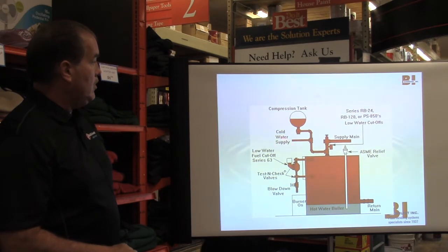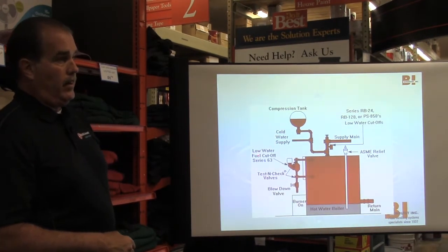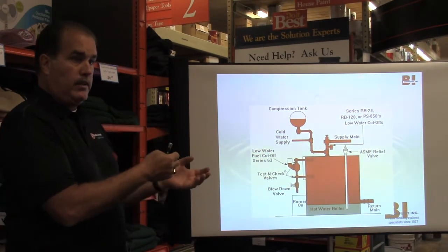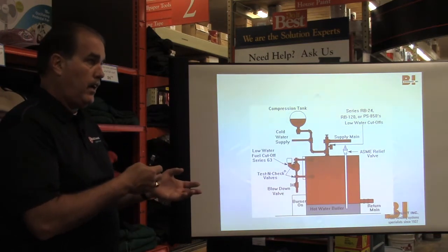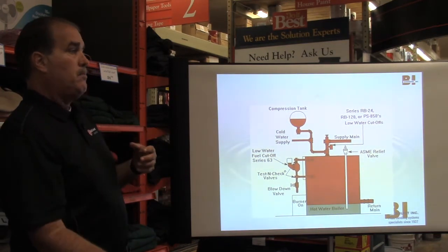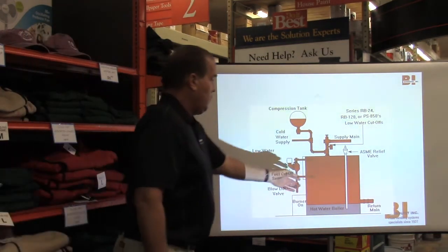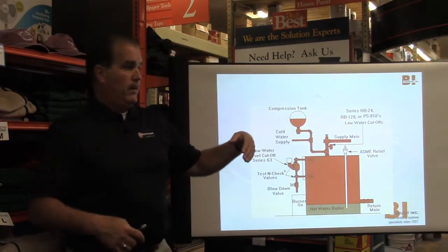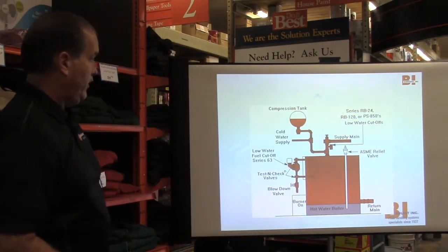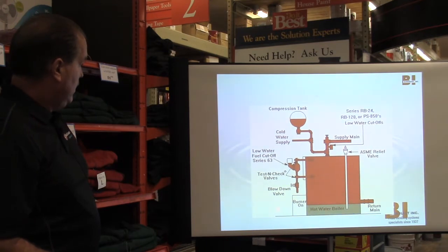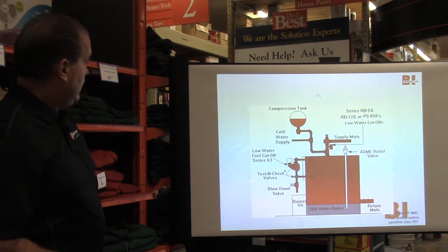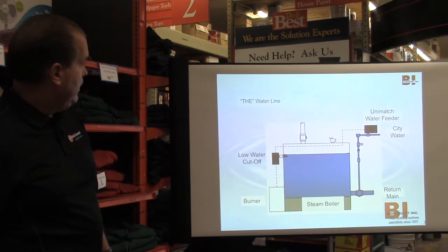This is your inlet water. You usually will have a makeup regulator that actually lets the water in. It's usually set for like 12 psi or whatever. So if the system water on the boiler side drops low enough, it'll let the city water in. And that's about it on that.